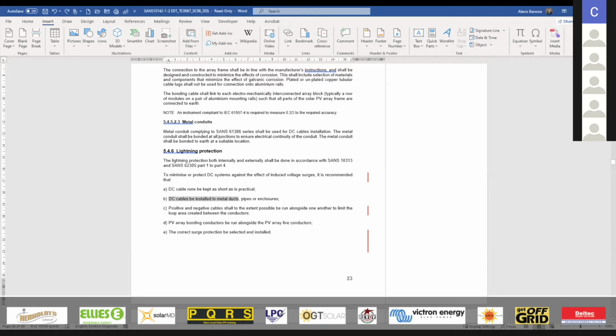Another interesting part, which we are really trying to advocate, is that if ever possible, always keep the DC cables inside metal ducting, metal trunking, or a metal wireway that's at least covered to 80% by steel, leaving only 20% air. Putting it into a wire basket that's more air than steel is not the same. So we've got to try and get these things into galvanized conduits, or into what's quite common on the rooftops, metal ducting, like a cable tray with a lid on top. And the simple reason is it builds a cage. Everyone knows the Faraday cage as a concept, but it builds a cage which shields your DC system or even your RS-485 communication system from the induced lightning effects that would be present on a solar system.